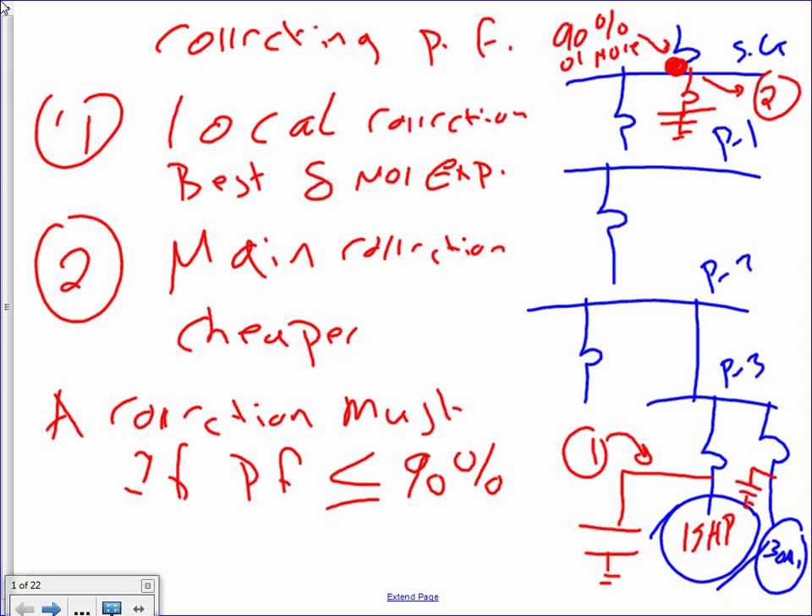Here's the situation. I have a switchgear that feeds panel one, panel two, panel three. Panel three has two motors — one is 15 horsepower, one is 30 horsepower. So when I do correction, there are two ways of correcting power factor. One way is correcting at the level of the offender — right where the offenders are. The offenders, when it comes to power factor, are motors.